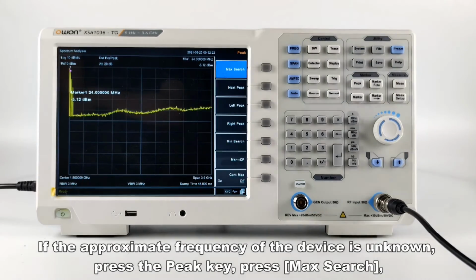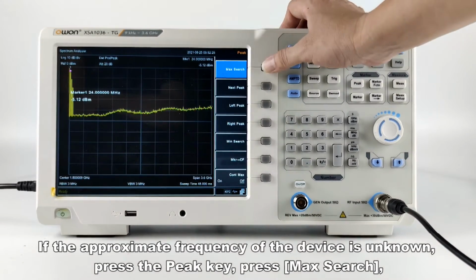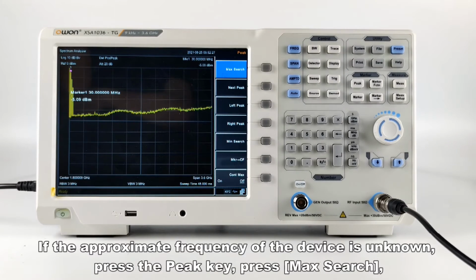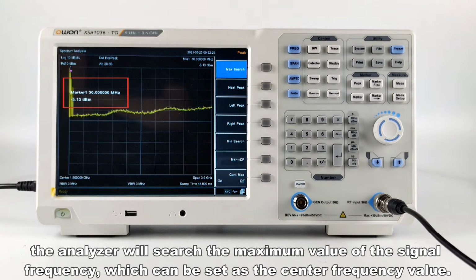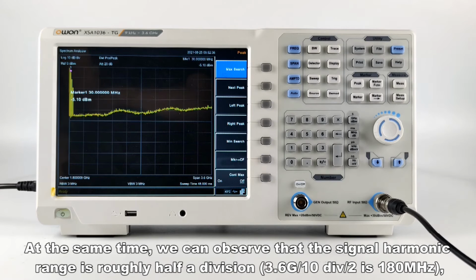If the approximate frequency of the device is unknown, press the peak key. Press max search, and the analyzer will search for the maximum value of the signal frequency, which can be set as the center frequency value. At the same time, we can observe that the signal harmonic range is roughly half a division.